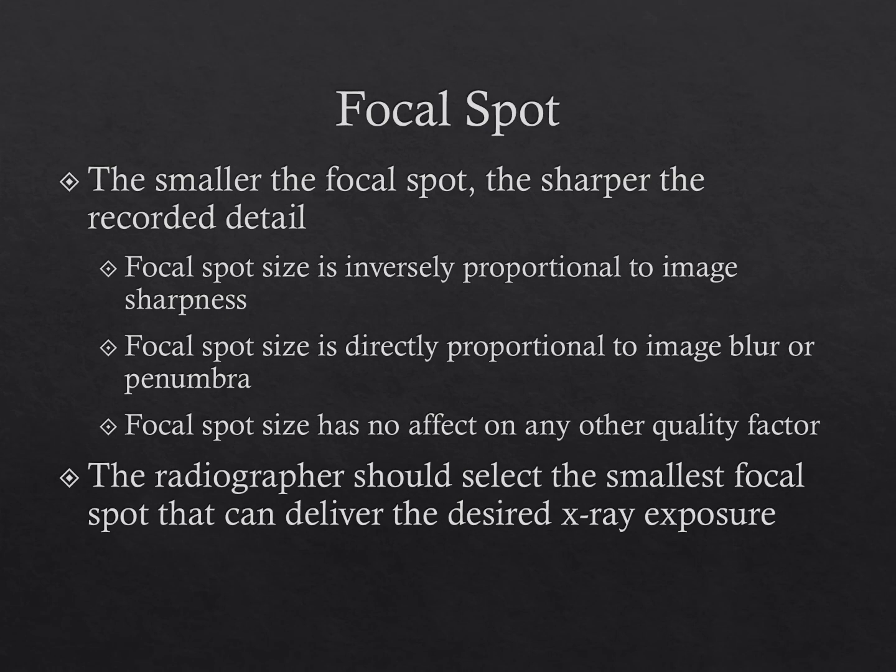It's very difficult to see the difference between the focal spots. Now, maybe in the past, when they had very large focal spots because of the type of target they were using, this might have been a bigger factor on the sharpness of the image. But with today's equipment, I would challenge anybody to actually see the difference between using the small focal spot and the large focal spot with the digital techniques that we have today.